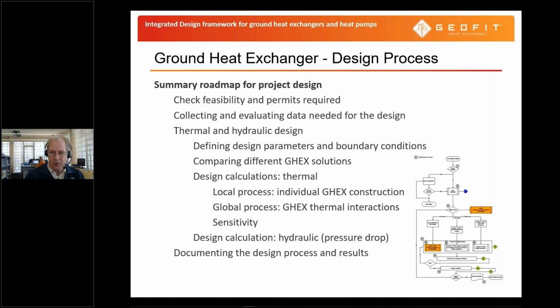And in the calculations, we have to look at the local process, the individual ground heat exchanger, and then we're talking mainly about the construction of the borehole or the slinky type heat exchanger, and looking at the parameters such as fluid flow, fluid type, and how that translates to the borehole thermal resistance. And then we have the global process, where we start looking at interactions between individual loops, and at the end of the day, also the sensitivity of this design. Part of the design calculation is also the hydraulic part, mainly the pressure drop and the pumping power associated with this. And like I said, at the end, we want to document the design process and the results of the design for the end user, for the owner of the system, but also, for instance, for regulatory bodies to make sure that they know what has been installed.